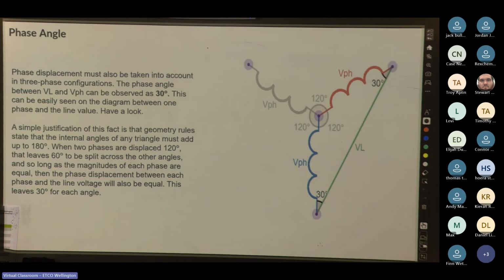Yep, you've got parts of the answers there. Cool. So by rotating a magnetic rotor through 360 degrees, 3 separate coils positioned 120 degrees apart each produce an alternating voltage. Together they form 3 out-of-phase waveforms, or the 3-phase system. Cool. So each phase winding of a star-connected system produces 230 volts. What will the line-to-line voltage be?